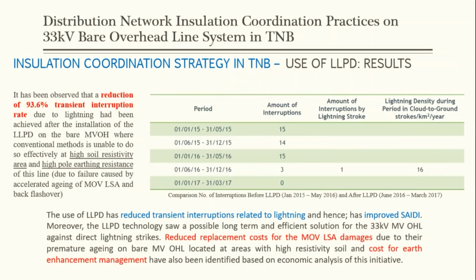Okay. Secondly, we found out that with the use of the LLPD, it has reduced transient interruptions related to lightning and hence has improved SAIDI. Moreover, the LLPD technology is seen as a possible long-term and efficient solution for the 33 kV medium voltage overhead lines against direct lightning strikes. It also helps to reduce replacement costs of MOV line surge arrestor damages due to their premature aging on bare medium voltage overhead lines located in areas with high resistivity, and costs for earth enhancement management have also been identified based on economic analysis of this initiative.